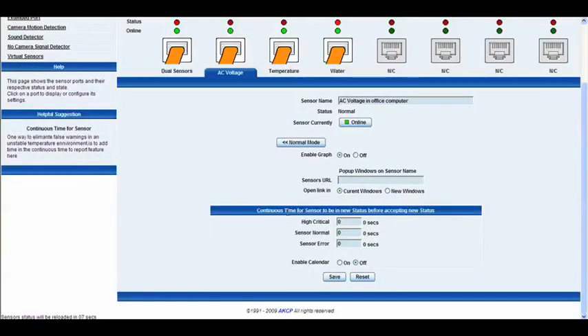Below that we have the continuous time — the duration for the sensor to be in a new status before accepting that status. For example, if the sensor goes into a high critical status for five seconds, once it's been in that status for five seconds, it will then display the high critical status. The same applies for normal and also for sensor error.